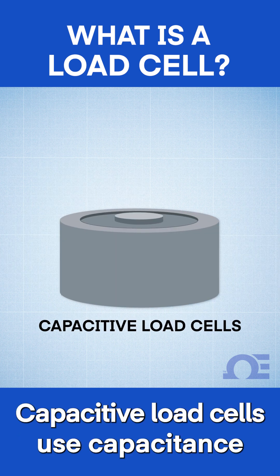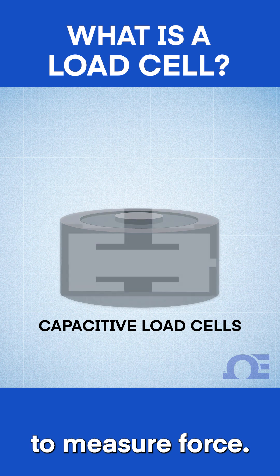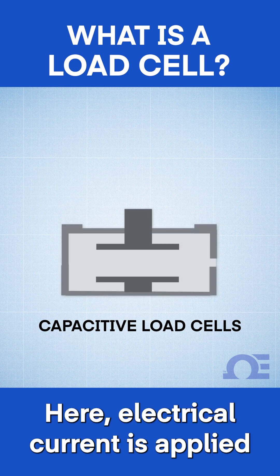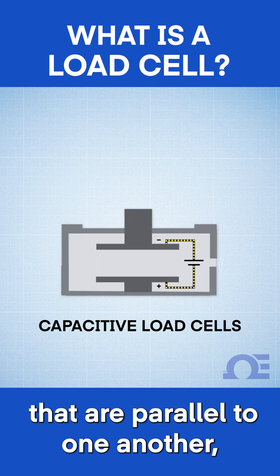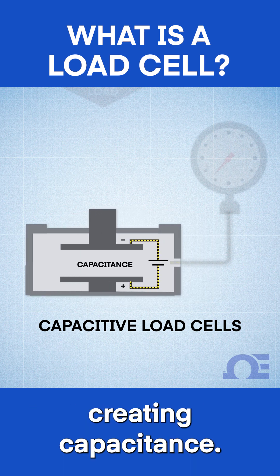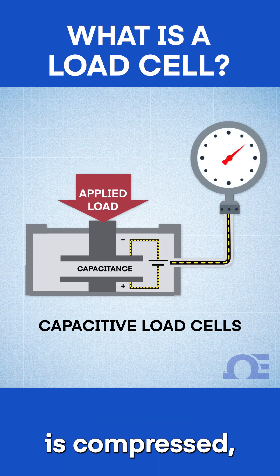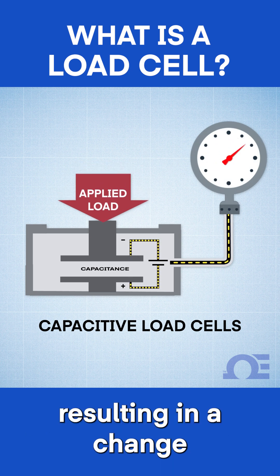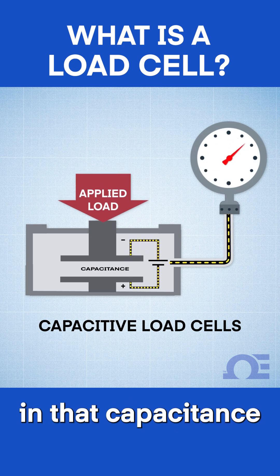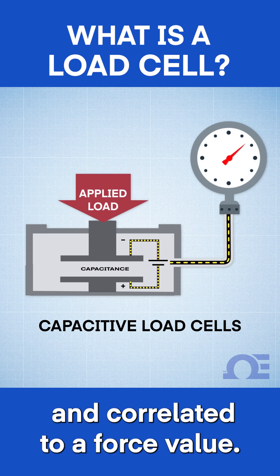Capacitive load cells use capacitance to measure force. Electrical current is applied to two flat plates that are parallel to one another, creating capacitance. When weight is applied, the gap between the plates is compressed, resulting in a change in that capacitance that can be measured and correlated to a force value.